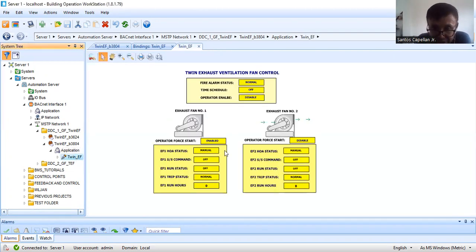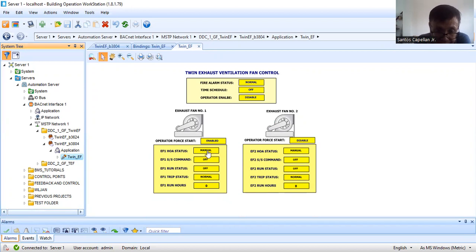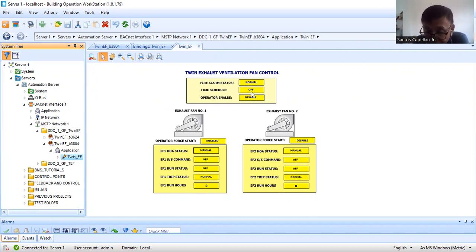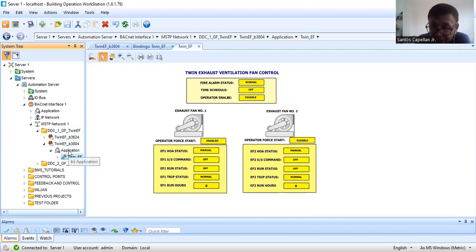I've already created the graphics here — 'Twin Exhaust Ventilation Fan Control.' Some of the points already created in our controller include: hand/off/auto, start command, run status, trip status — the same things for EF2. Also EF1 run hours, operator force start, operator enabled time schedule, and the same points for EF2.